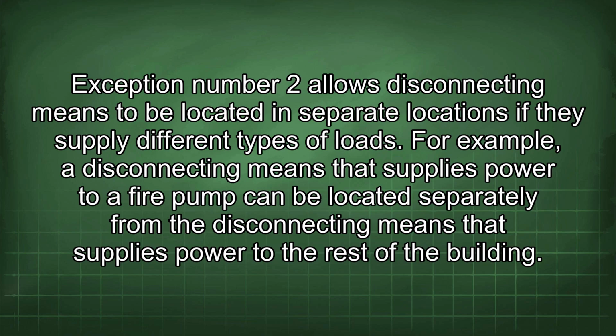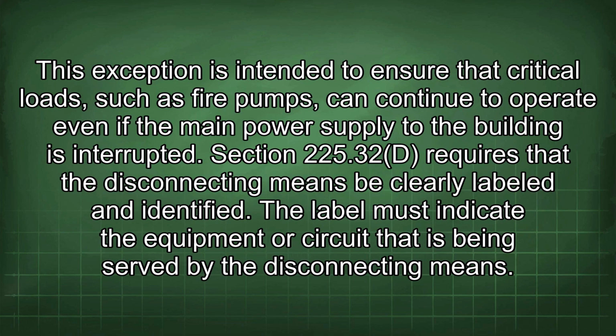Exception number 2 allows disconnecting means to be located in separate locations if they supply different types of loads. For example, a disconnecting means that supplies power to a fire pump can be located separately from the disconnecting means that supplies power to the rest of the building. This exception is intended to ensure that critical loads, such as fire pumps, can continue to operate even if the main power supply to the building is interrupted.